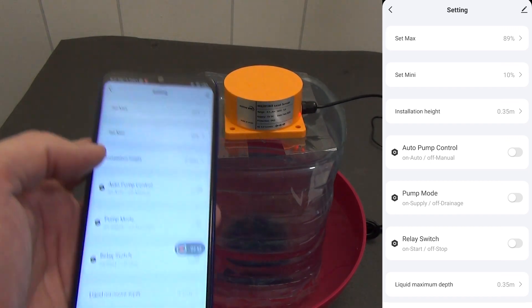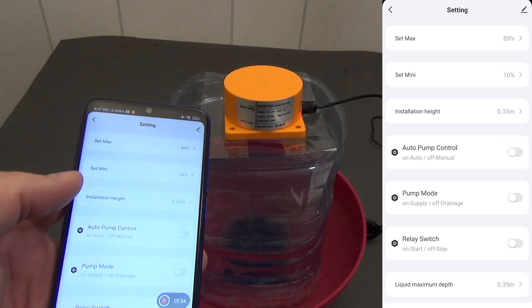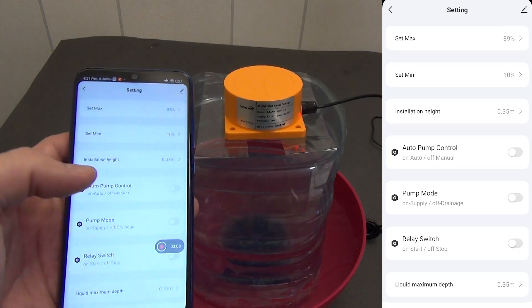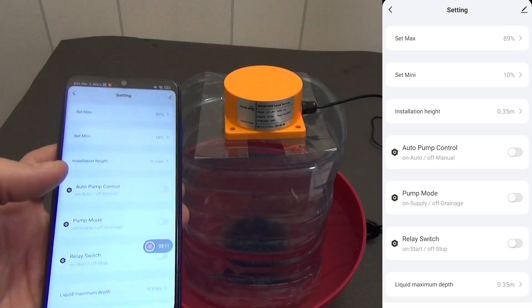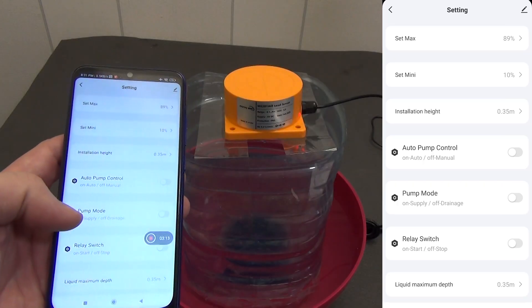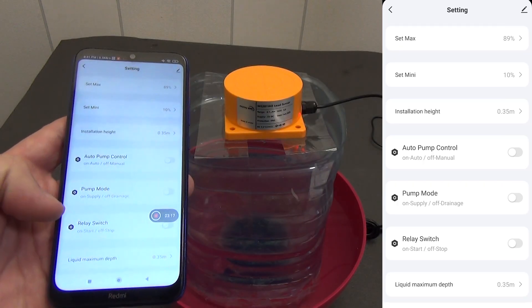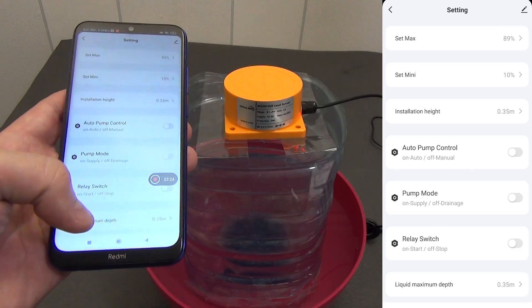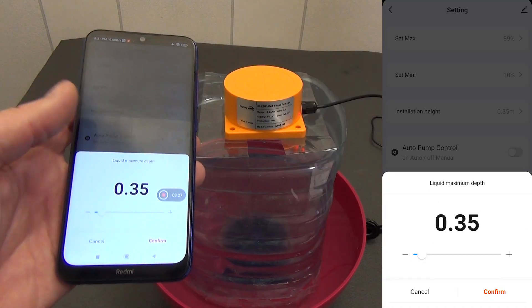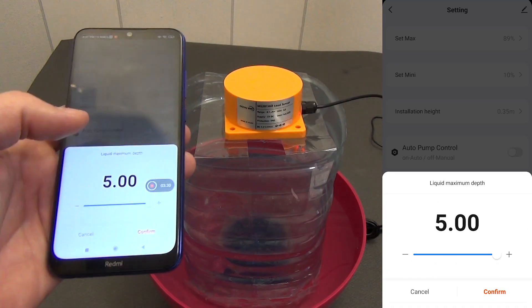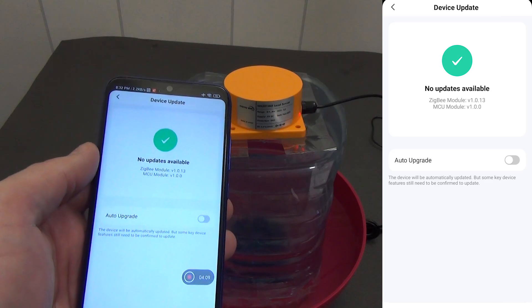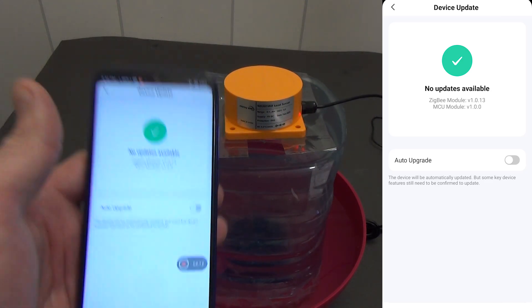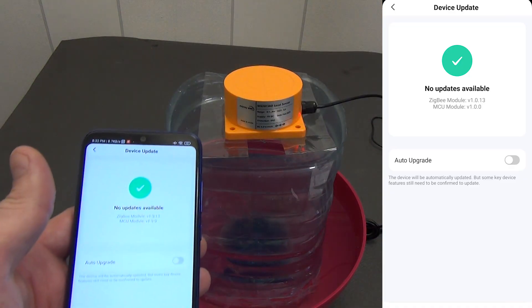The following parameters do not apply to this model, but I think that there are other models with a built-in relay models for connecting external devices. Here we see the following settings: Automatic pump control can be enabled so that the system itself turns on or off the pump. Pump mode, pump mode filling or draining. Relay switch, a relay that controls the pump, switching the operating mode. The maximum liquid depth is 0.35 meters. In fact, 5 meters is the maximum level that the sensor sees. All alarms, trigger limits and even pump automation are all configured directly in the application. That is, in the future you cannot approach the equipment at all, everything is already smart and autonomous.